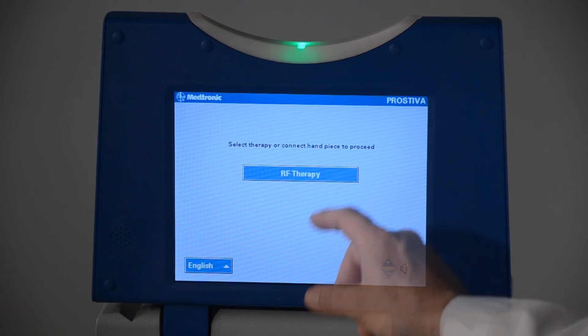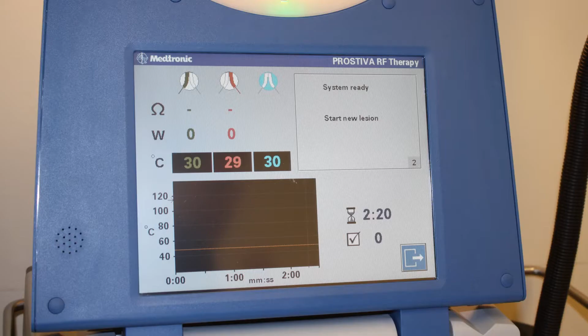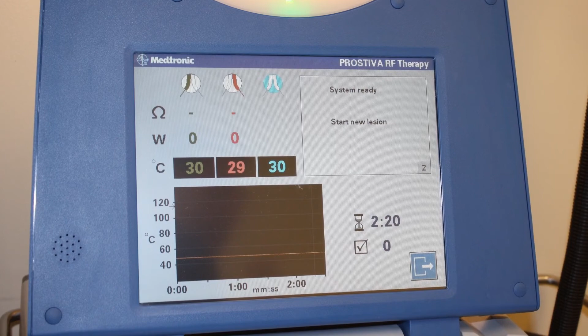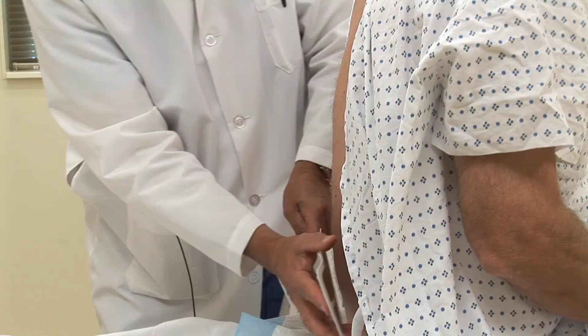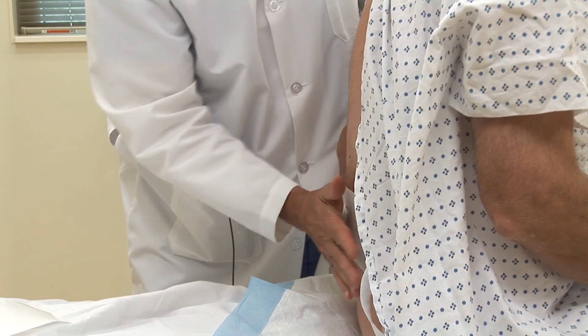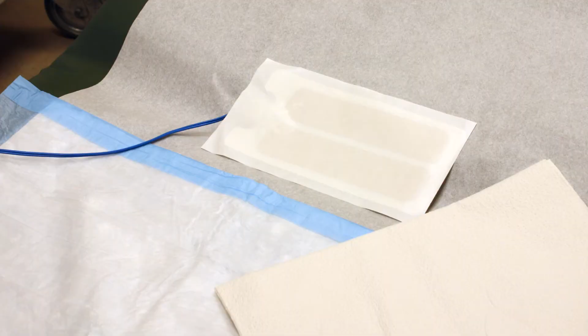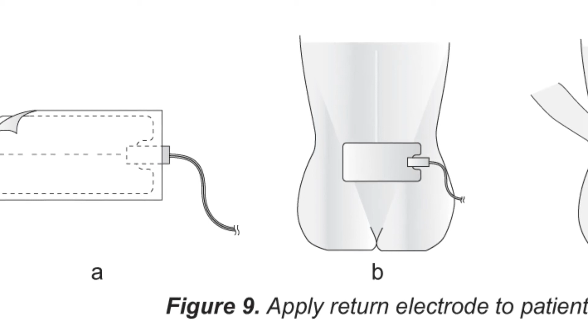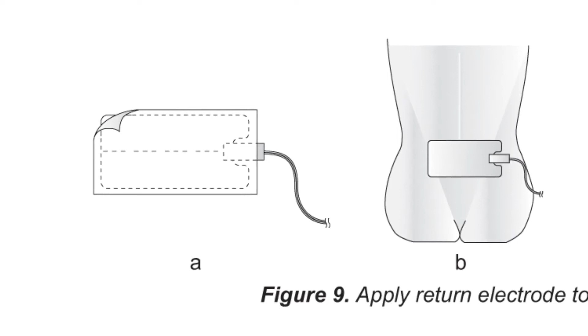Make sure the Prostiva RF therapy screen is displayed and then press the Therapy button. Confirm that the System Ready message appears on the screen. At the start of the procedure, a nurse will prep the area and attach the grounding pad, also known as the return electrode, to the patient's lower back. The return electrode has a self-adhesive surface that secures it to the patient's skin. The return electrode provides a relatively large electrode area. This helps to reduce the density of the return current flow from the handpiece to the patient's skin.